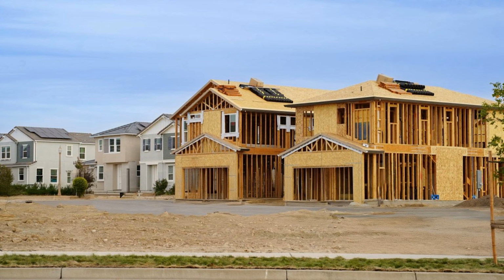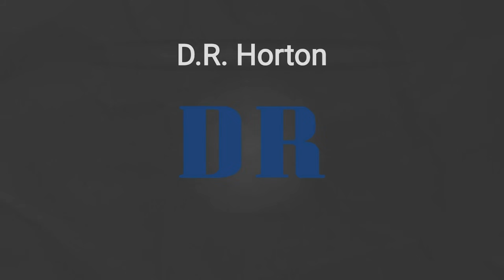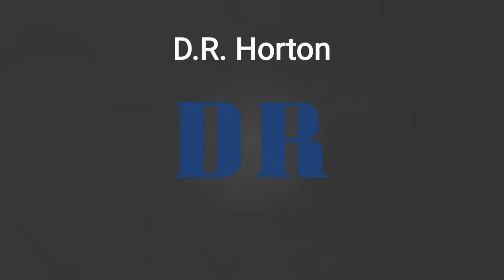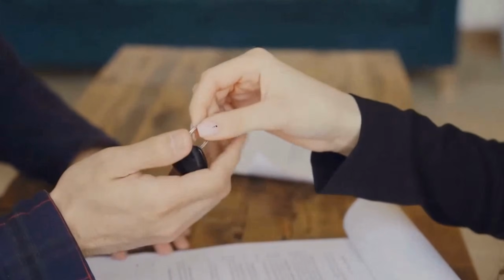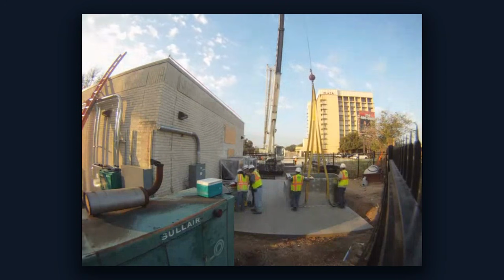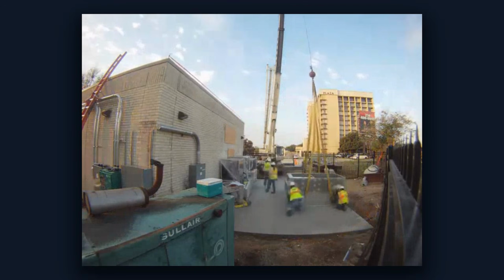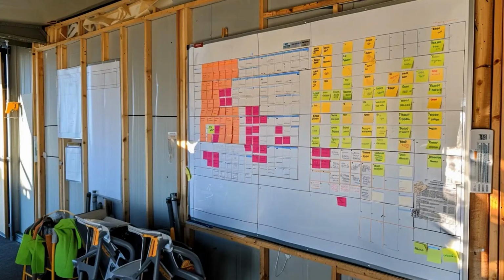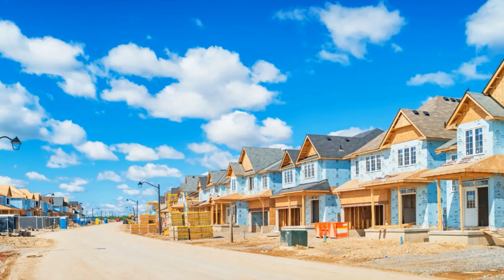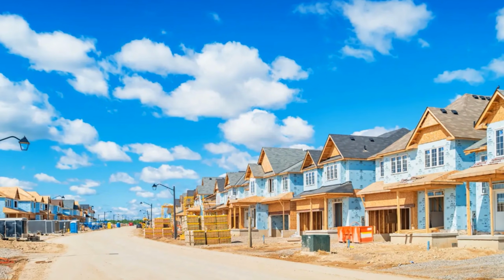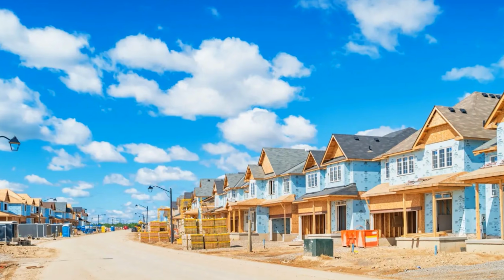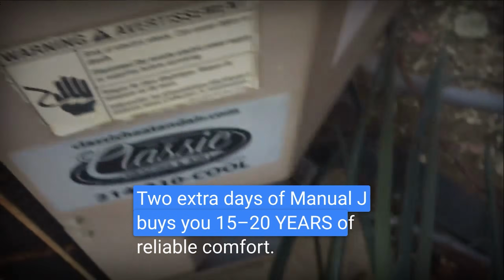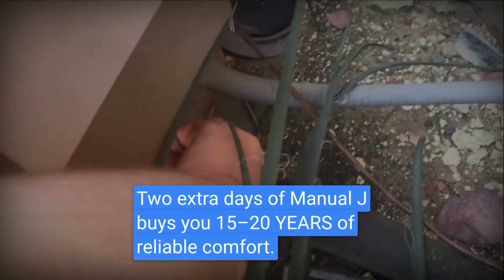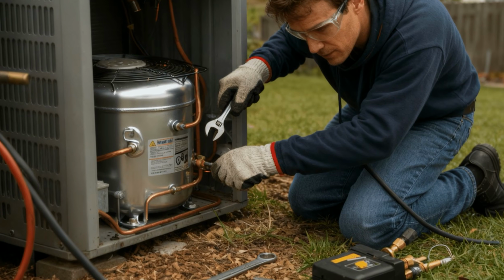Because the largest production home builders in the country, D.R. Horton, Lennar, Pulte Group, Taylor Morrison, pay their HVAC subcontractors by the house, not by the hour. The faster the subcontractor installs, the more money they make. A proper Manual J-based system takes 4 days to design and install correctly. The expedited rule of thumb installation takes 2 days. That 2-day difference represents the gap between a system that will last 15 to 20 years and a system that will burn out in 10.